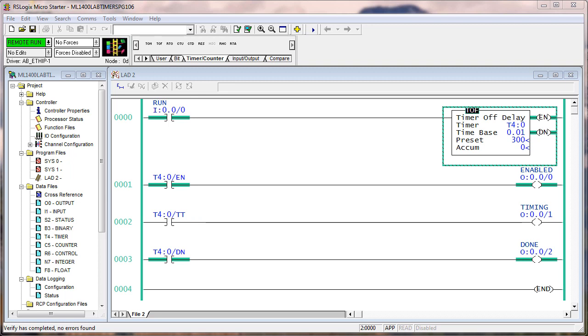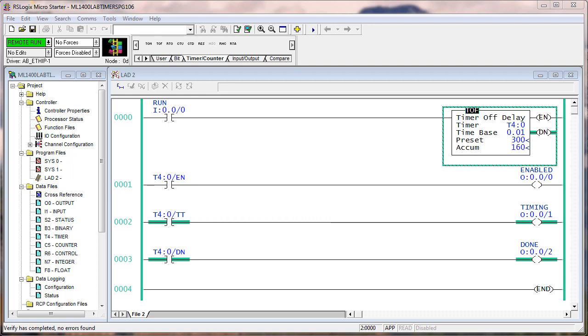So what we're looking at, in all fairness to the creator of this instruction, they're looking at a delay after the done bit goes off. Let's start the timing here. So I'm going to turn it off. Done bit is still on, and the done bit is going to go off three seconds after the input went off.